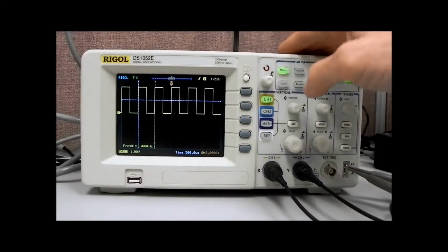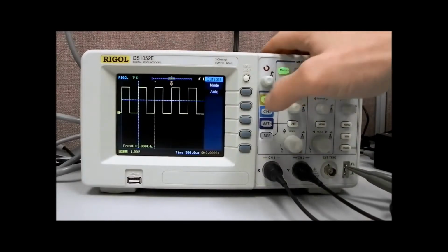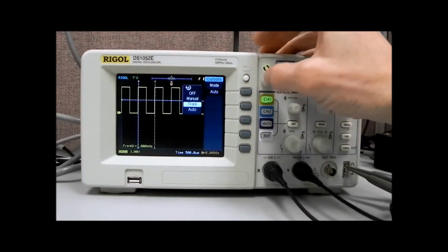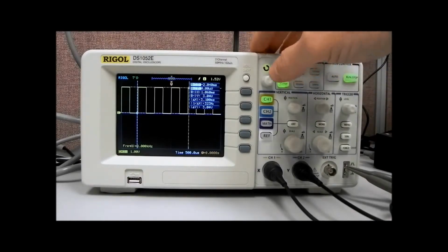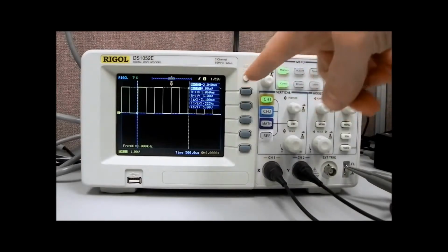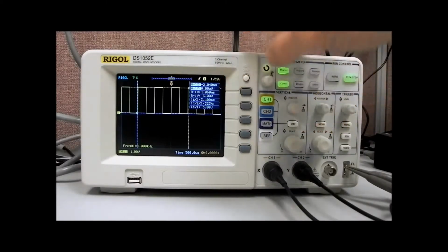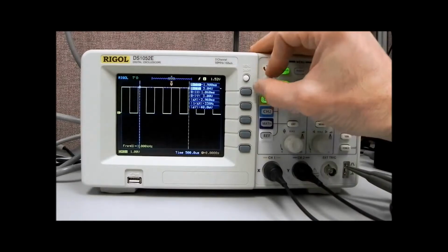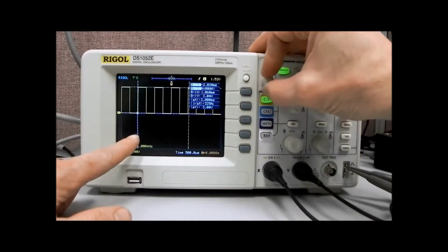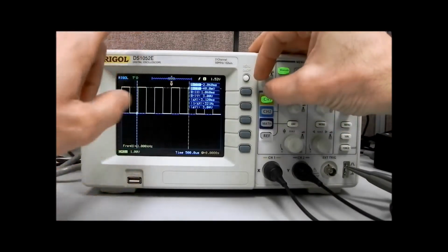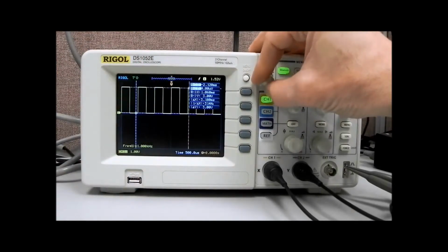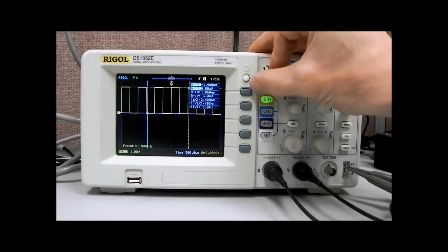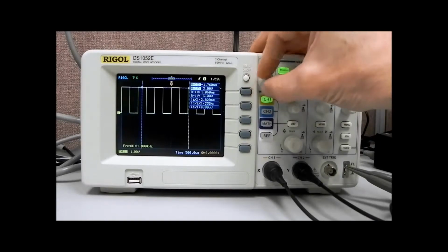Now let's take a look at some of the other cursor measurement modes. Let's go to cursor, and then out of auto, let's go to track. And what tracking is going to do, as you can see, it's actually moving along with the signal. I've collapsed the menu for that particular function, but you can see as I rotate along, I'm moving the cursor, and the cursor actually has a time as well as an X designation or cross there, and you can see it's following the waveform, so you're getting coordinates or locations on the waveform display based on the waveform itself.